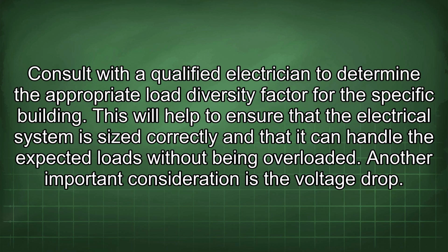Consult with a qualified electrician to determine the appropriate load diversity factor for the specific building. This will help to ensure that the electrical system is sized correctly and that it can handle the expected loads without being overloaded. Another important consideration is the voltage drop.